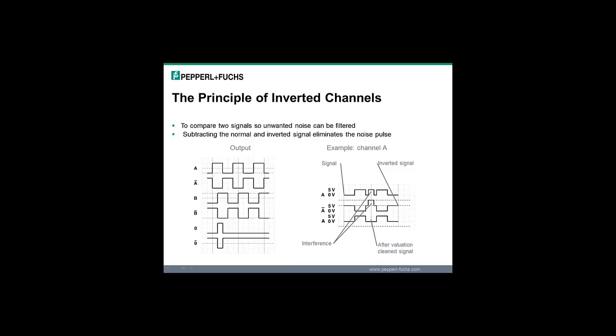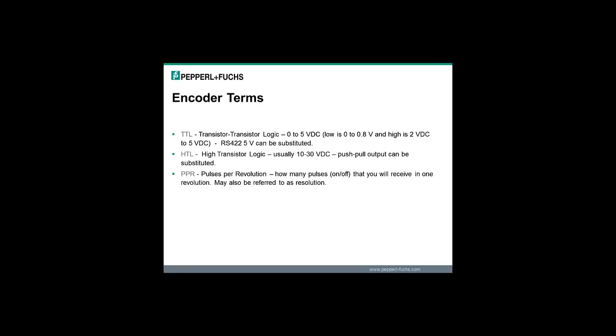The encoder with inverted channels of A, B, and zero are used so unwanted noise can be filtered. A device such as a controller or PLC will subtract the normal and inverted signal to eliminate the noise pulse. A few common encoder terms are TTL, HTL, and PPR. TTL is an acronym for transistor-transistor logic. This is for a 0-5 volt DC range where 0-0.8 volts is a low and 2-5 volts DC is a high. The RS422 output can be used if a TTL output is requested. The HTL is an acronym for high transistor logic. This is usually 10 to 30 volts DC and push-pull output can be substituted.